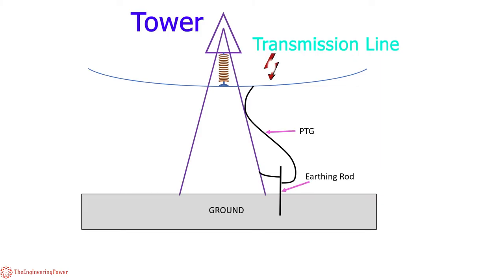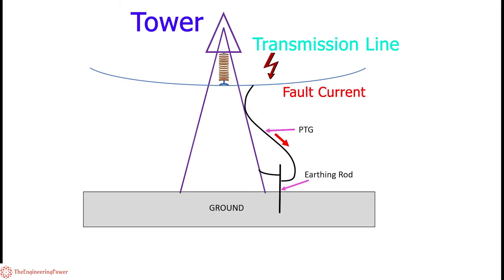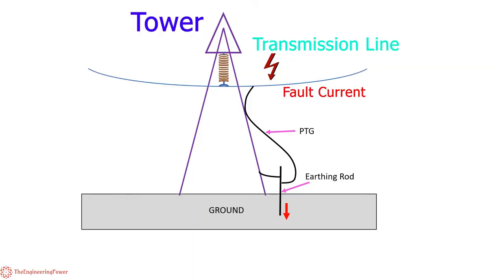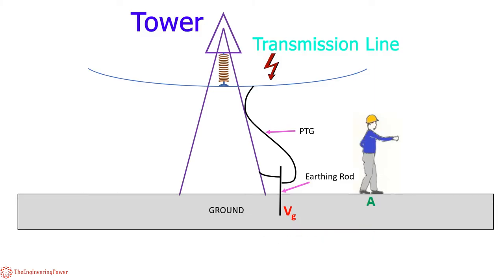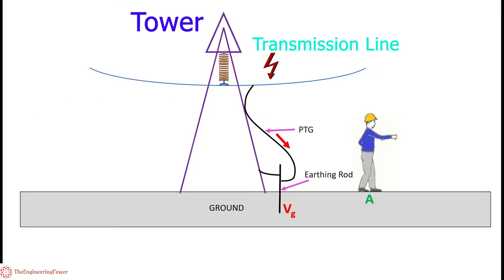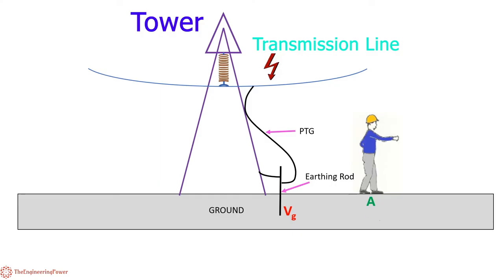Now in case of a ground fault on a transmission line due to any reason, the fault current will flow to the ground through the PTG and the ground voltage rises. This voltage decreases as we move away from the ground rod in any direction due to the earth resistance. Consider a person standing at point A. Now, in absence of bonding, if a ground fault occurs, the person at point A will be at different potential than the ground potential.